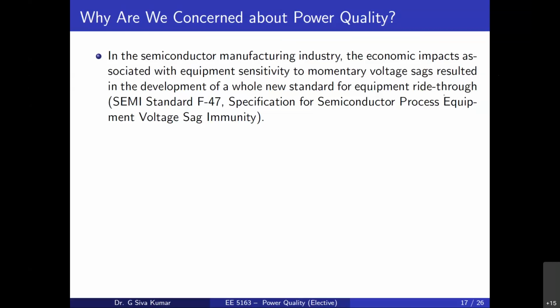This all depends upon the individual load also. Some systems, as I quoted in the last class, are capable of handling 50 percentage voltage variation for even 2 or 3 cycles. This particular study looked at how many cycles the semiconductor manufacturing equipment is able to withstand voltage variations for.